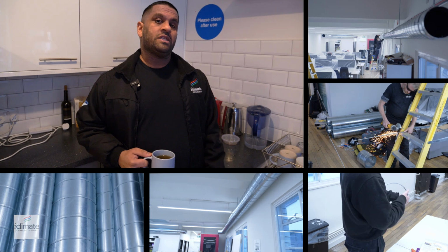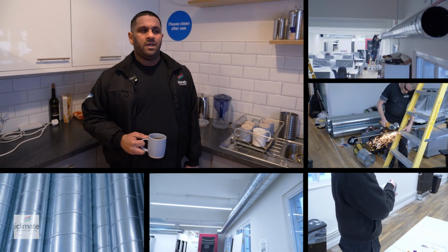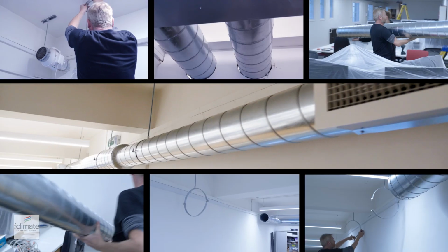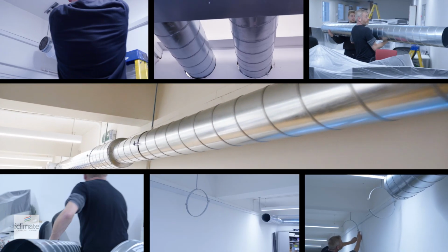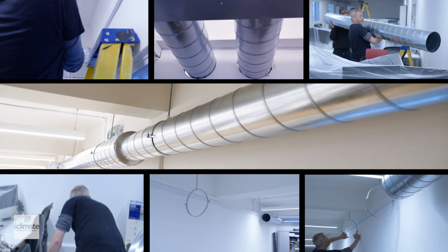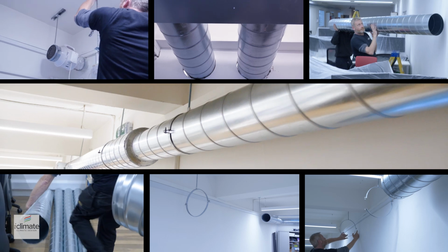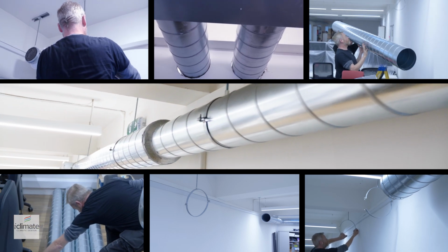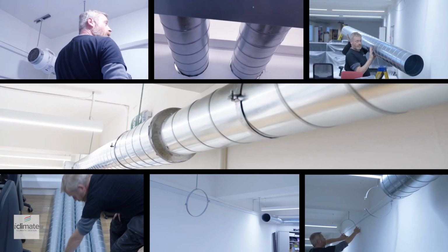You're joining me at one of our commercial sites today. We just completed a heat recovery ventilation project for this client. The job's in Farringdon and it's the time gap between Christmas and New Year, so nobody's here. What we did here was a mechanical heat recovery ventilation. So this office had no aircon, heating, no heat pumps, and no fresh air. The most important thing here is to get fresh air into that space.